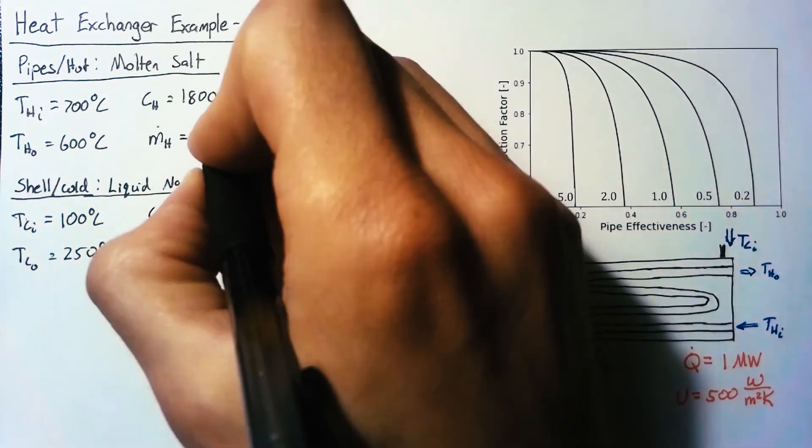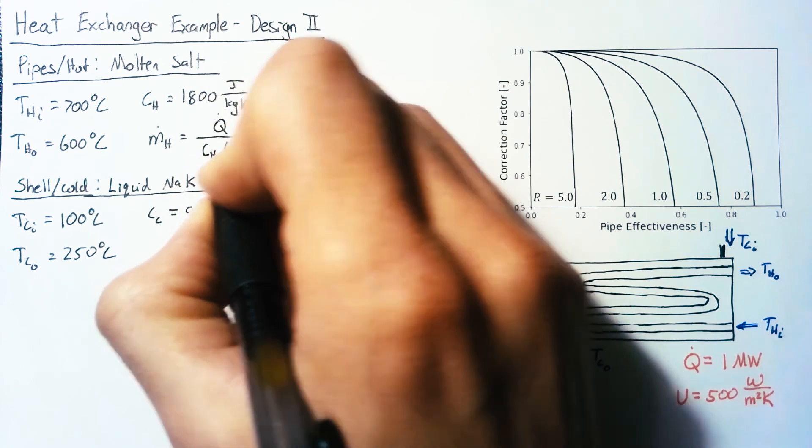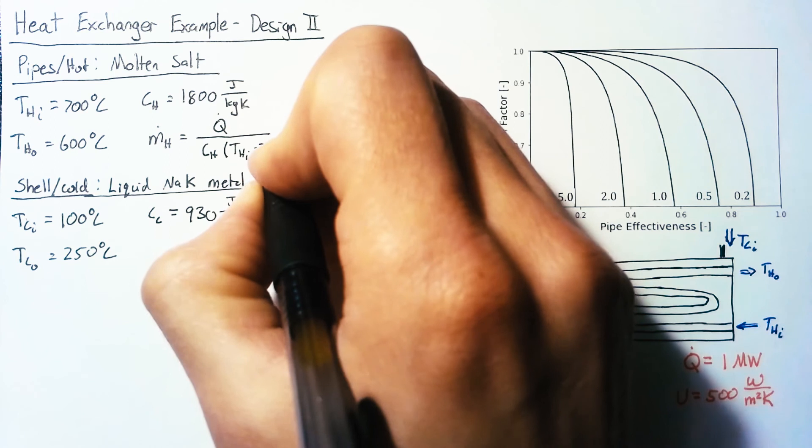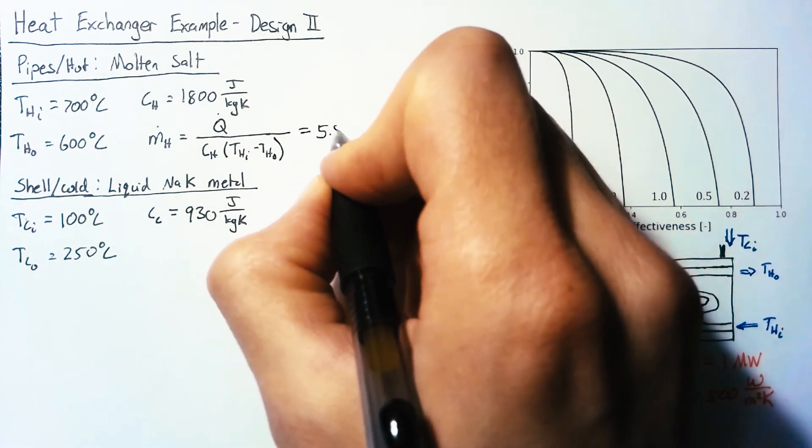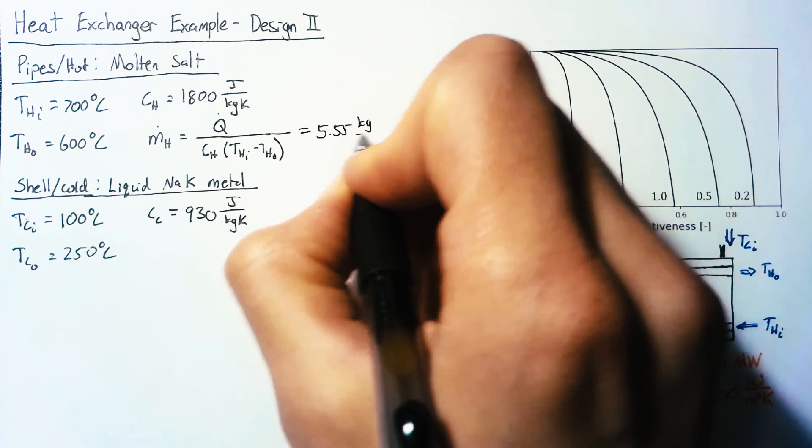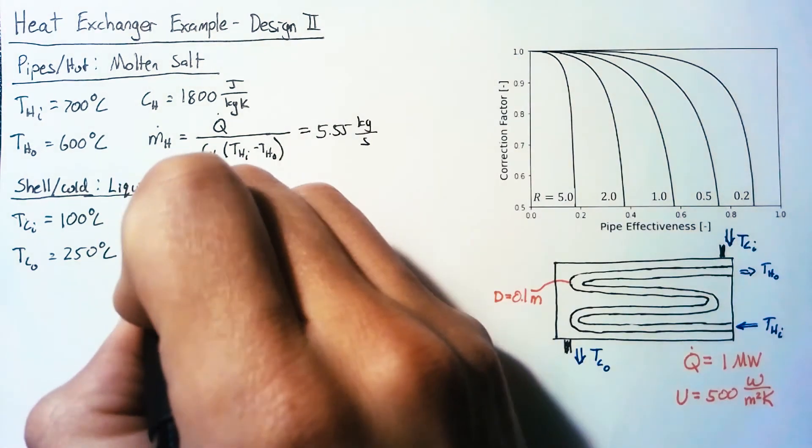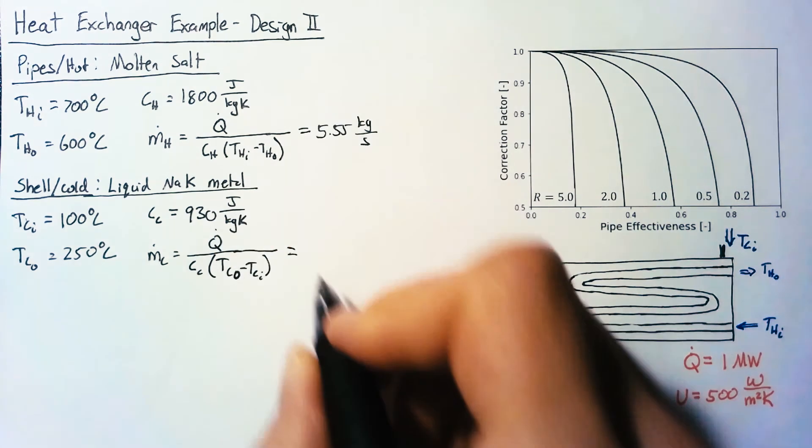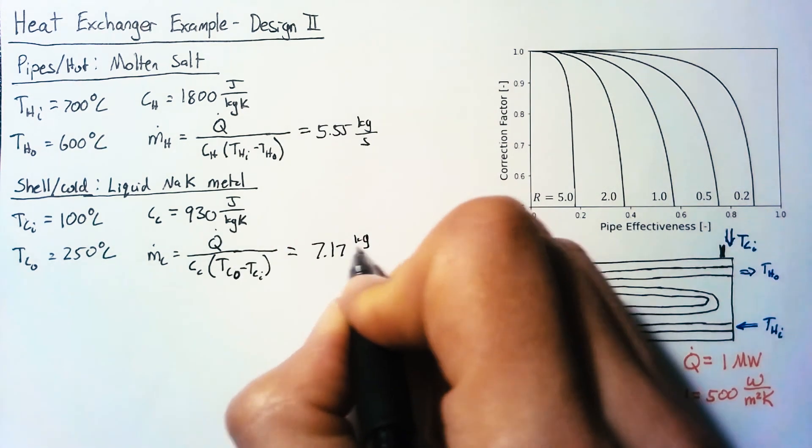So let's start off by finding our m dot values. m dot is just going to be our total heat transfer rate divided by our CH multiplied by our delta T, which is our TH in minus TH out. Plugging in those numbers, we end up with 5.55 kilograms per second. Then we can do the same thing for the cold side. This time, we're going to do TC out minus TC in, and those numbers give us 7.17 kilograms per second.